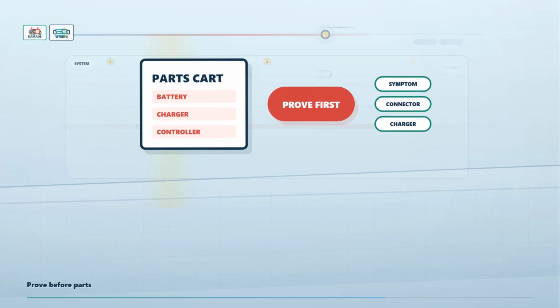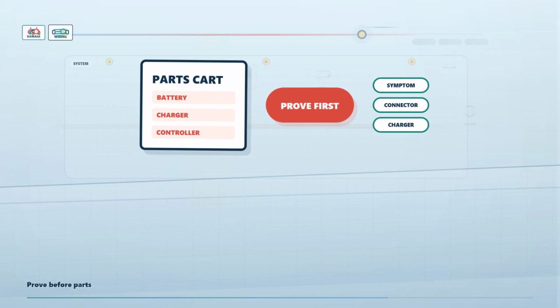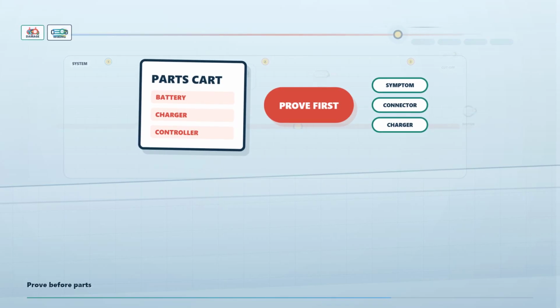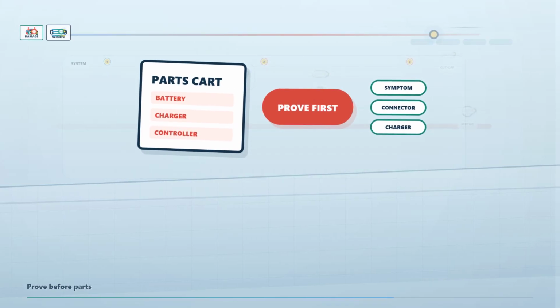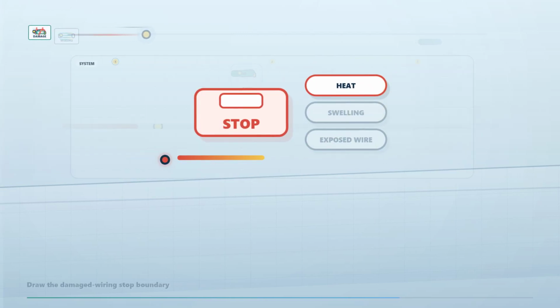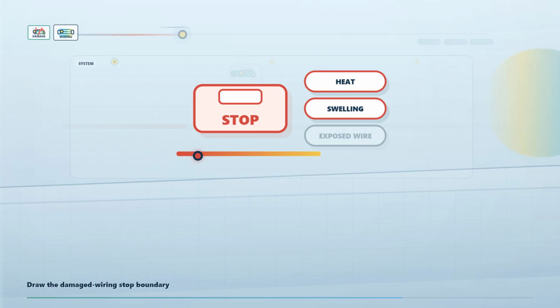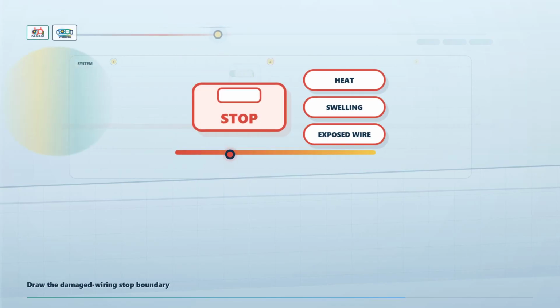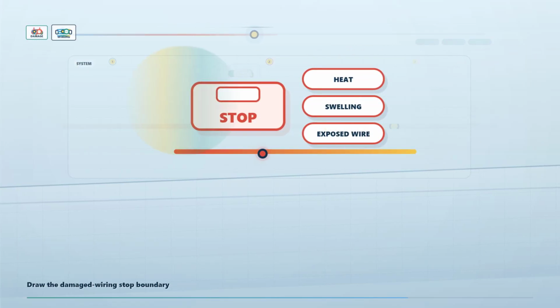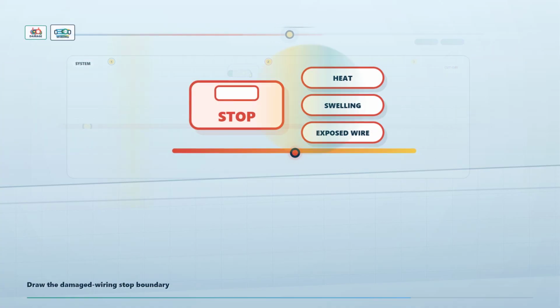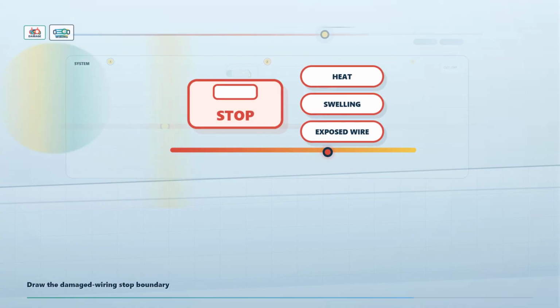There is also a clear stop line. If you see melted insulation, burnt connectors, exposed conductors, or signs of heat damage, stop the home diagnosis. That is no longer a simple symptom check. A damaged wire can create resistance, shorts, or intermittent failure, and those can make the controller path unsafe. At that point, the right move is professional inspection, not deeper trial and error.